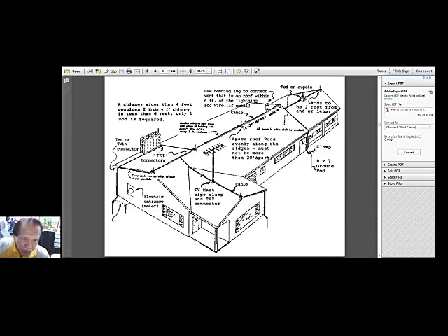But of course, the number of air terminals would be as many as you can. Maybe like in this, it doesn't really mention. Oh, it mentions here about 20 feet apart. 20 feet apart, so that's about 6 meters apart. 6 meters, 6 meters, 6 meters. So there will be so many of that.